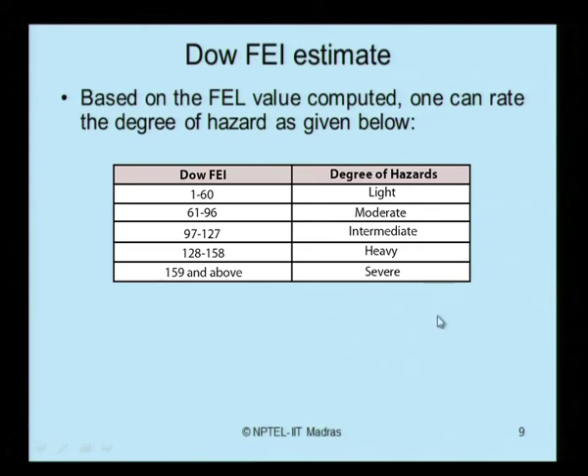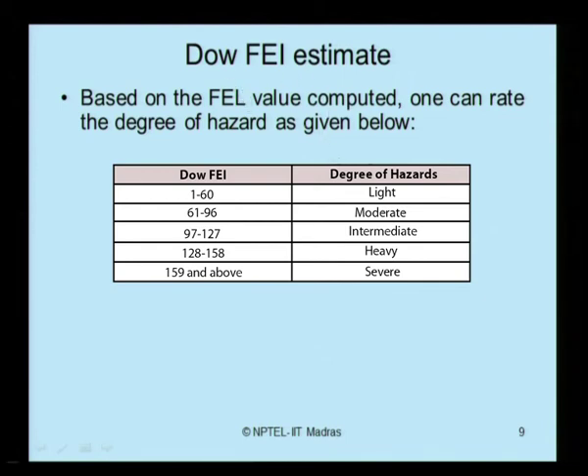Based on the FEI value, the degree of hazard can be classified from the table. If the FEI lies between 1 and 60, the degree of hazard from the fire and explosion index is classified as light. If it is greater than 159, it is considered severe.